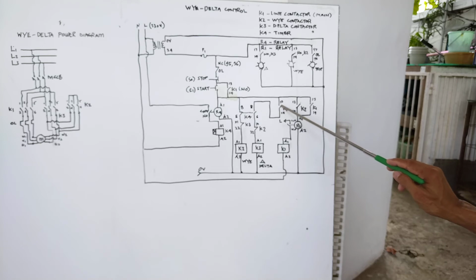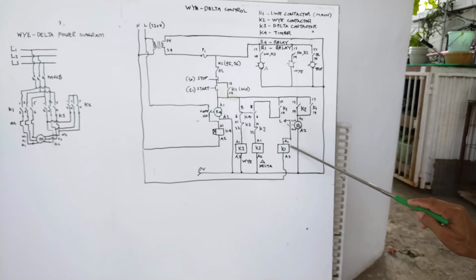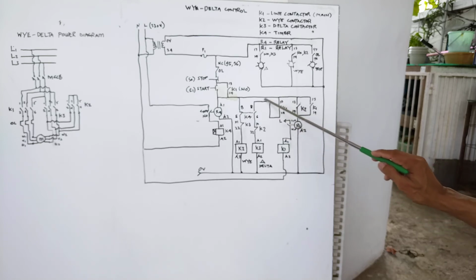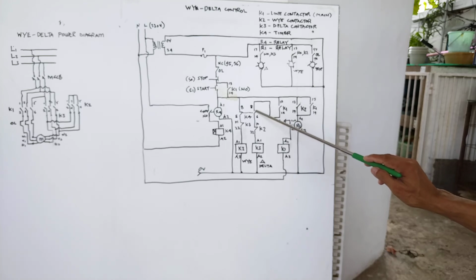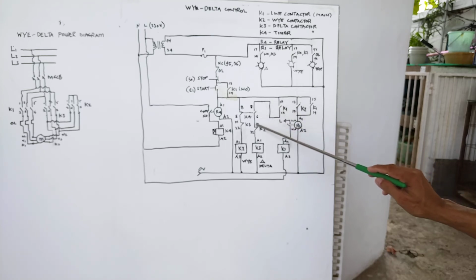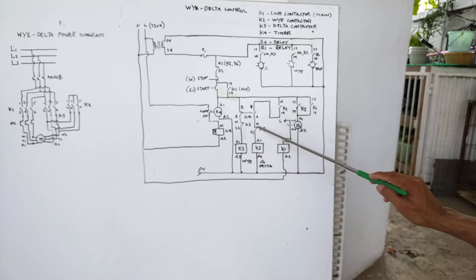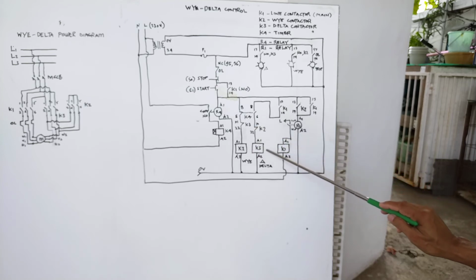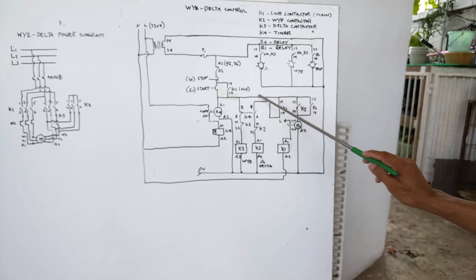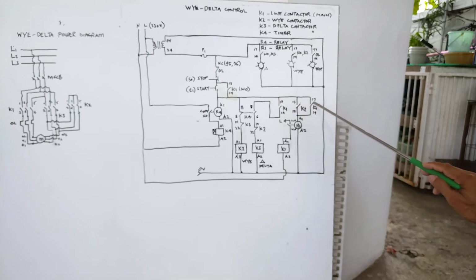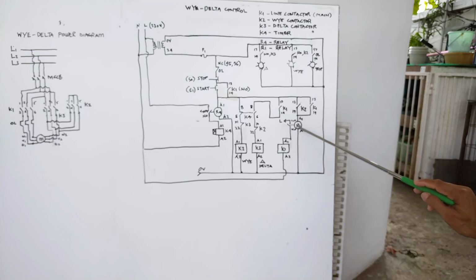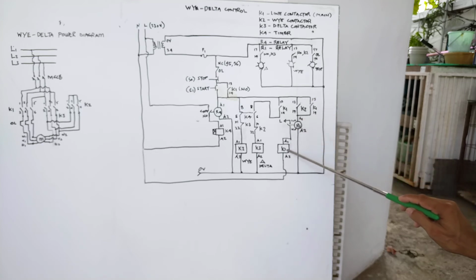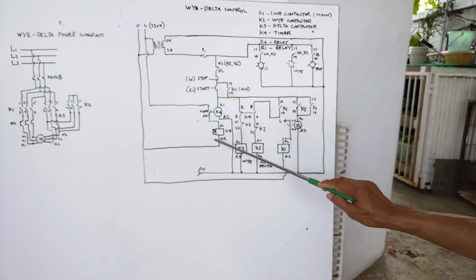But 24 volts will come here. Since this one is already closed, the first time this is energized, 24 volts will come here. Then this one, after the time delay, will close, so 24 volts will flow here. Then this K2 is de-energized, so this one is closed. So K3, the delta contactor, is energized. Now the 24 volts can still pass here, so it will keep on energizing our line, delta, and our timer.